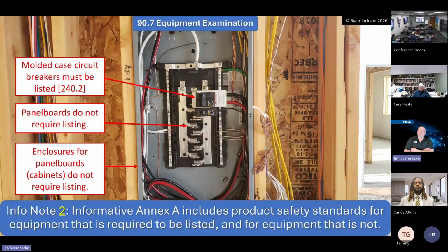One of the biggest mistakes made on drawings is 112 kVA transformers. The secondary conductors, because they're 400 amps into a disconnect or some sort of panel board, they'll always run 500s. And the plan reviewers will miss it and the designers will miss it. You cannot put conductors that have a 380 amp capacity on the secondary side of a transformer and terminate them into a 400 amp overcurrent device. In 240.21(C), it specifically says the next size up rule of 240.4(B) does not apply and cannot be used. So they have to be 100% or fully rated conductors, which means you have to have 600s. Good luck finding a panel board that accepts 600 kcmil.